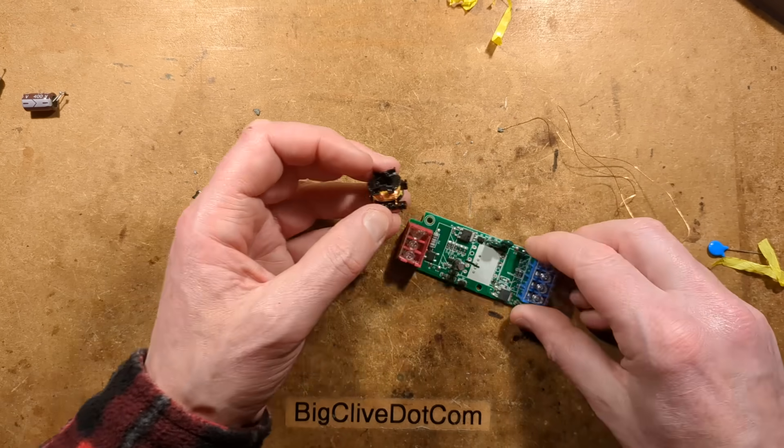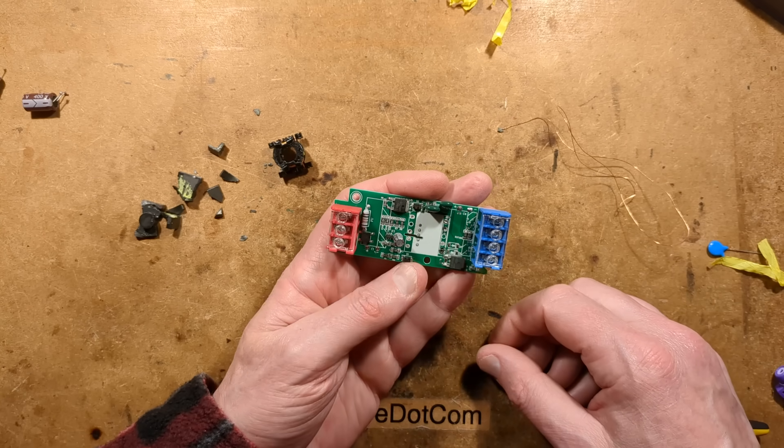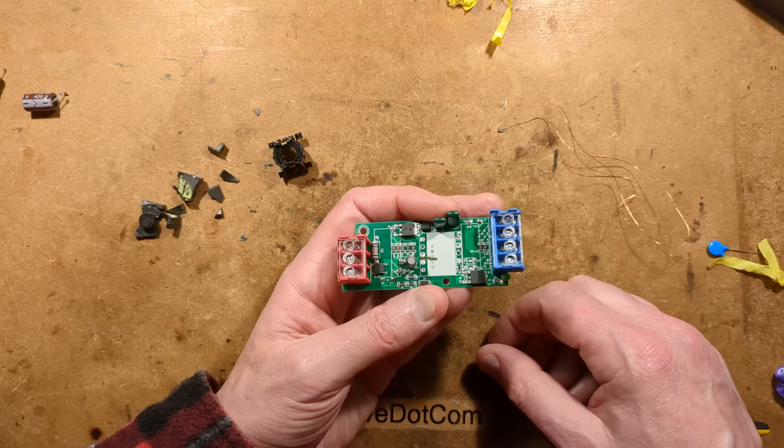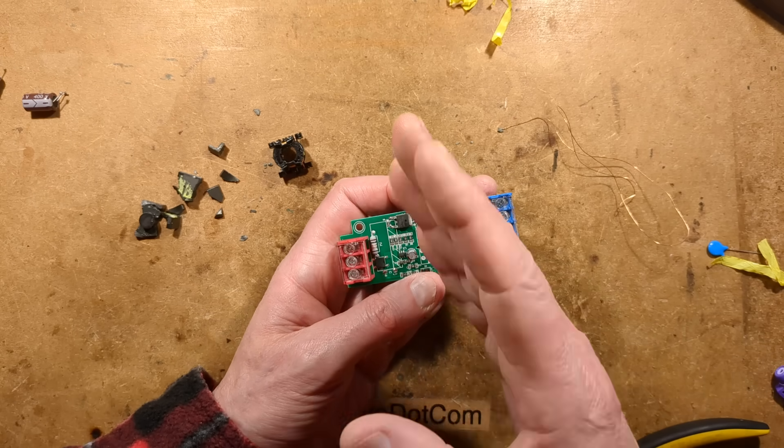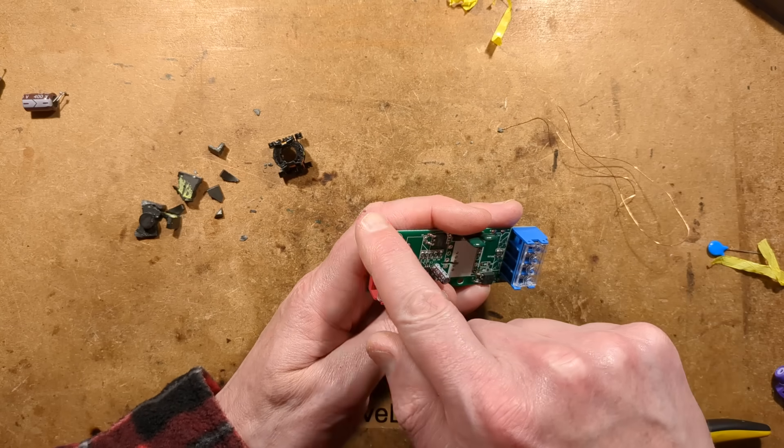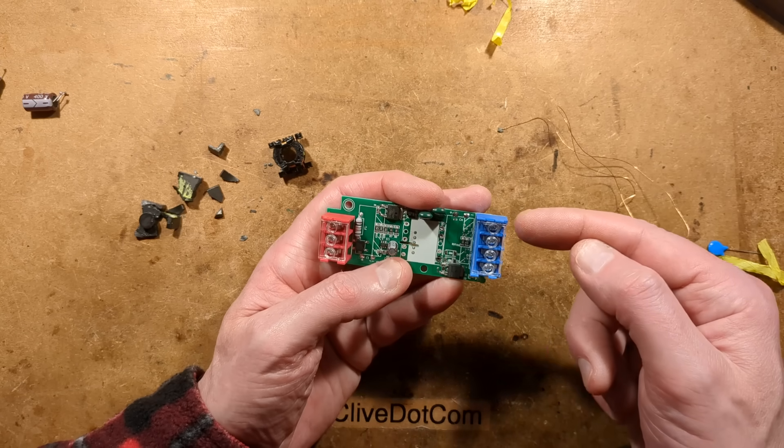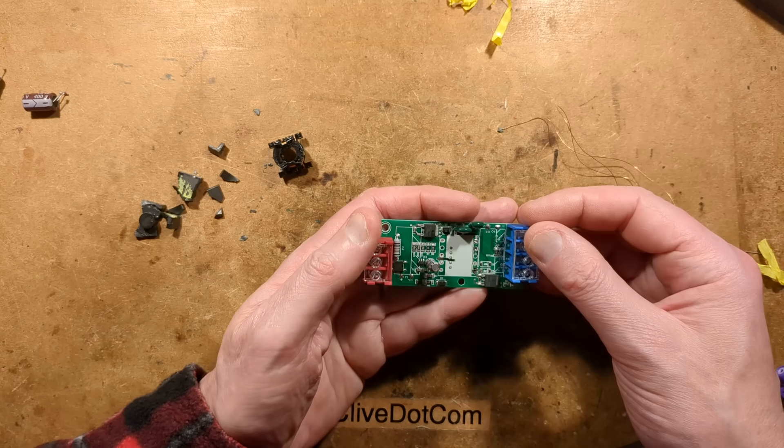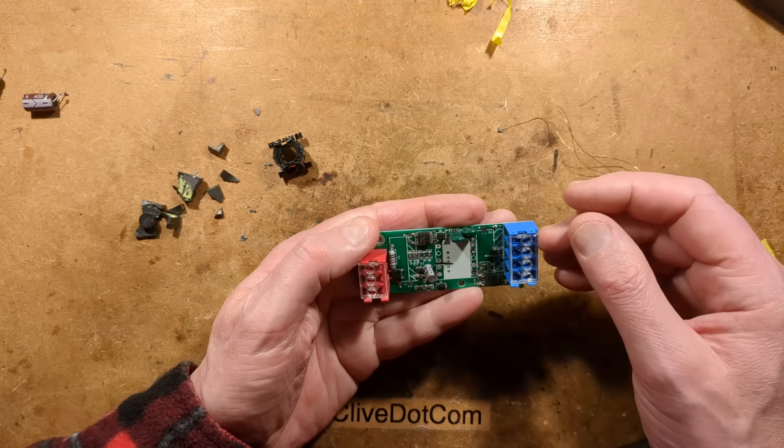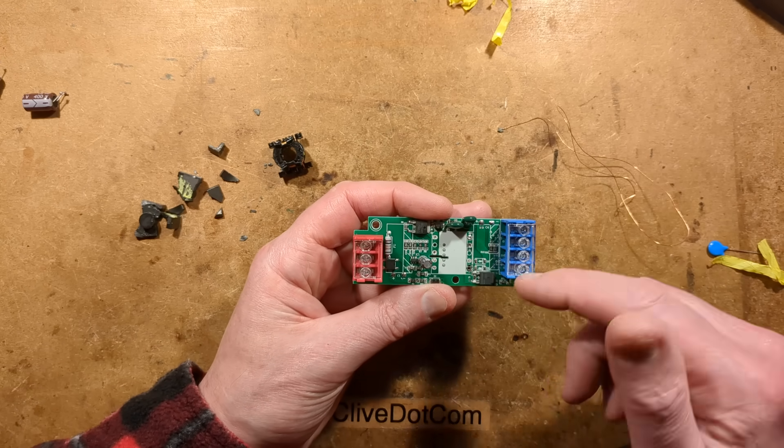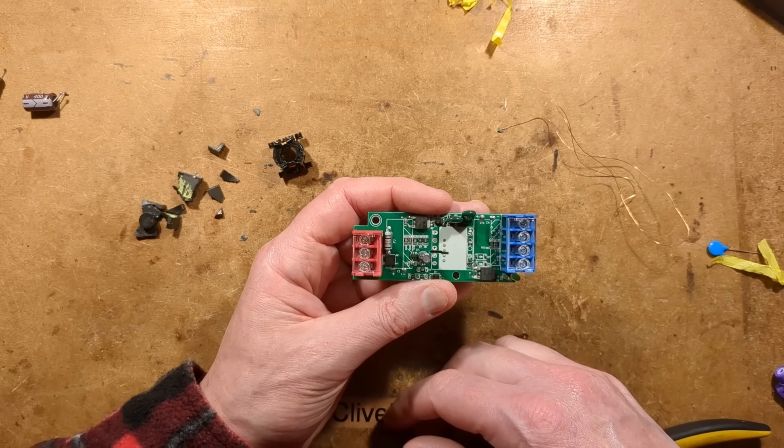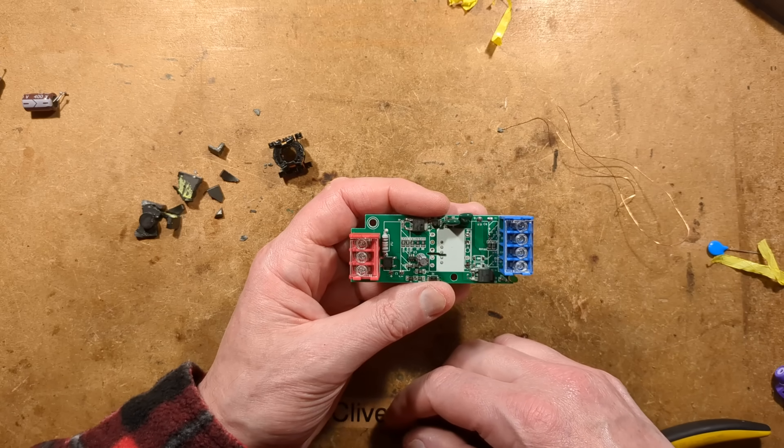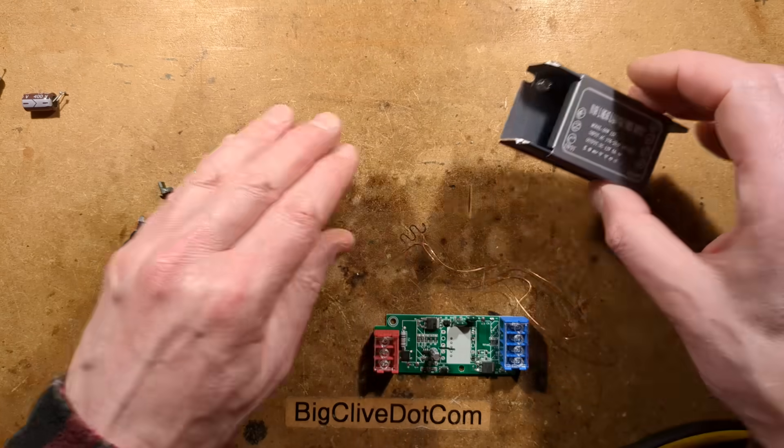So the only option here is to change the classification of power supply from SELV, Separated Extra Low Voltage, to Protected Extra Low Voltage PELV. Get an earth wire and use this terminal and loop it round and connect the negative. But that's not suitable for all applications. If you actually connect the negative to main's ground, then it means that when something goes wrong, it provides a fault path for main's voltage getting onto the low voltage side to actually trip breakers and stop you being fried basically.